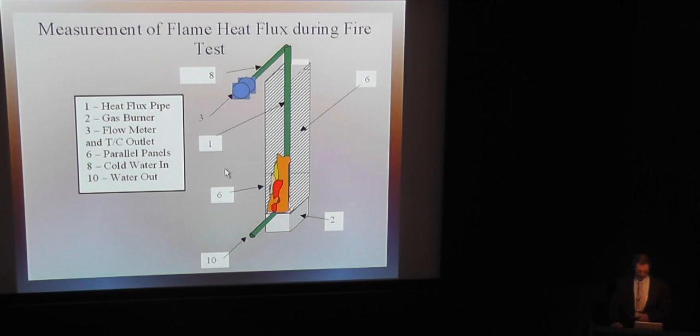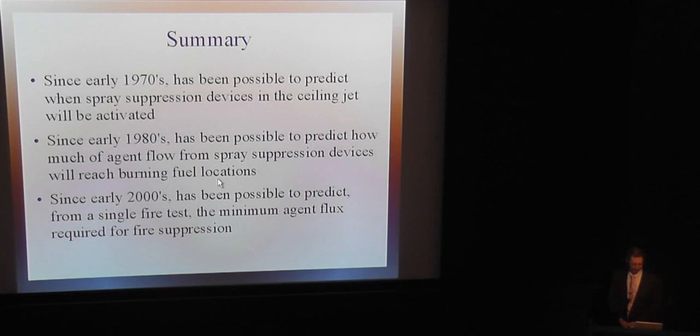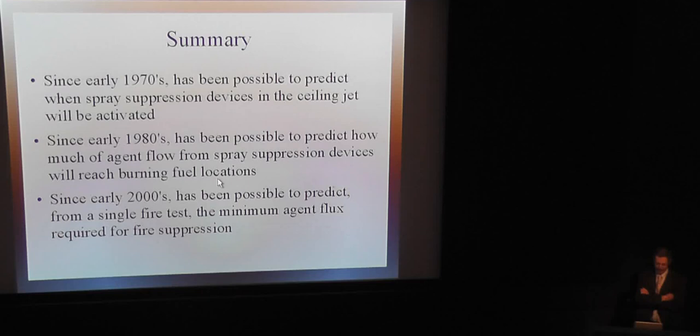Summarizing the work I did at FM over the years: since the early seventies, using the ceiling jet formulas, it's been possible to predict when devices near the ceiling would be activated. Then beginning in the eighties, you could do the spray-plume interaction and predict how much of the agent flow would actually arrive near the fire. And finally, in the 2000s, we've been able to predict from a single fire test the minimum agent flux you need for fire suppression. Thank you very much. It's really an honor to have been selected to give this talk, and I appreciate it deeply.